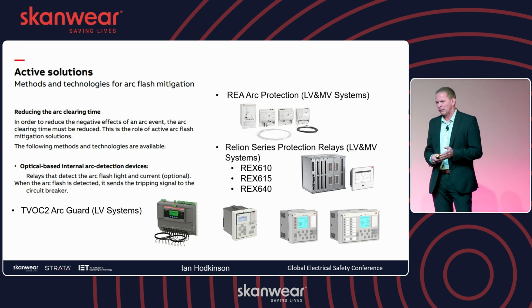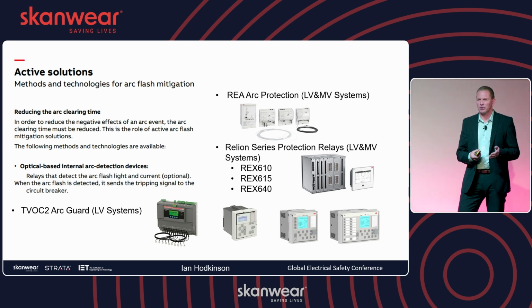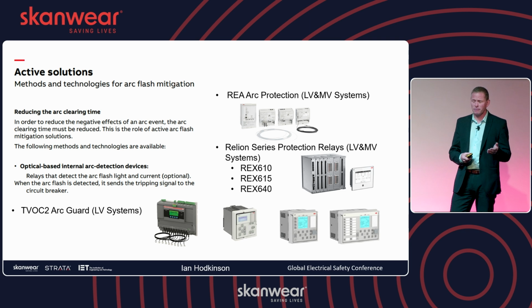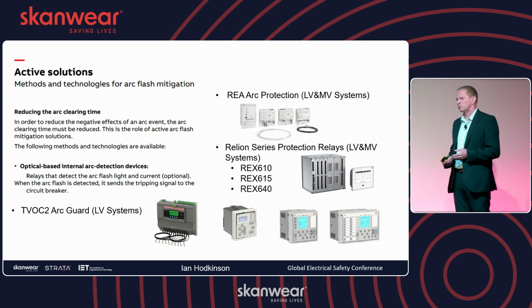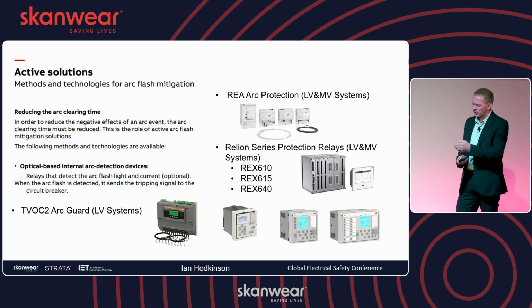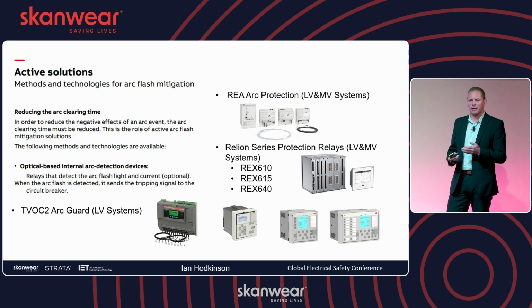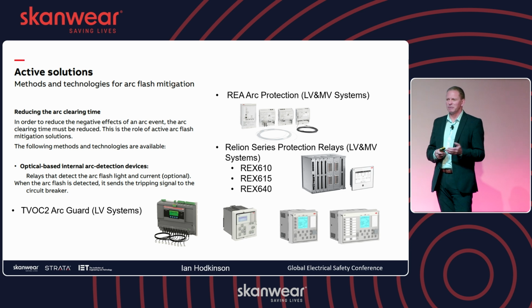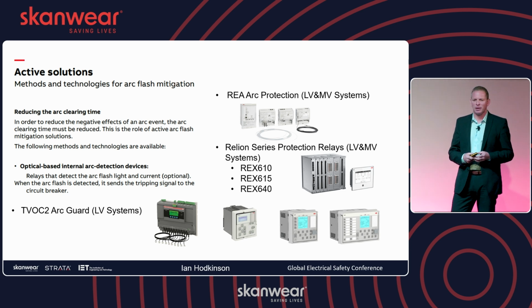However, in a lot of our new builds, we always have this now, a lot of customers are saying, well, let's just do arc protection from day one. It's a very small and insignificant cost. You're going to be fitting protection relays, and most modern protection relays nowadays, especially ours in the Relion family, have integrated arc protection, and you could do that over Ethernet comms, so it's the fastest communications between unit to unit, incomers to feeders or feeders to incomers, to break and to sectionalize and to be clever in how you do your tripping for the board.